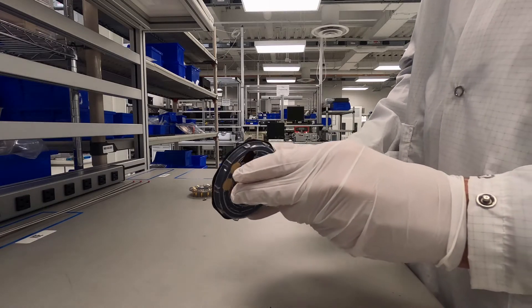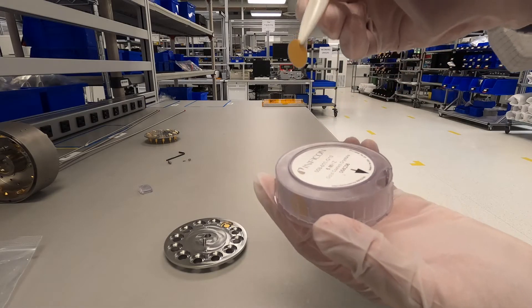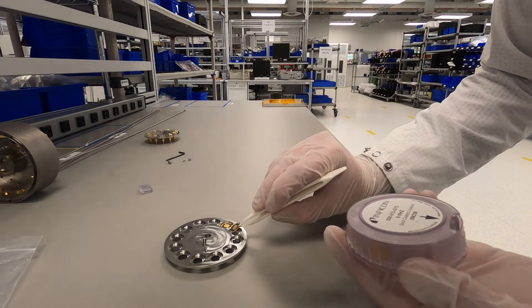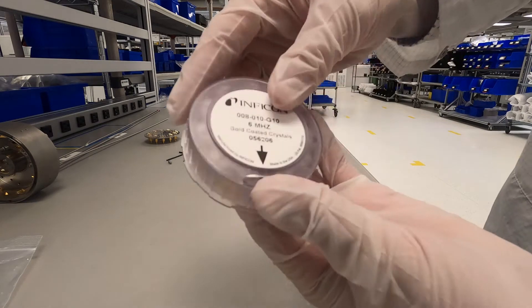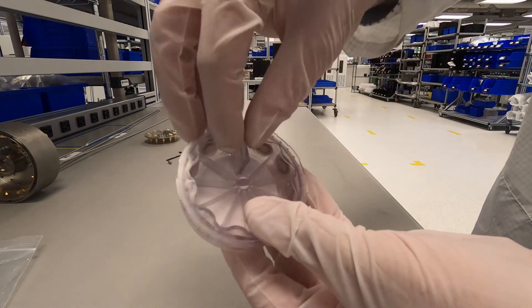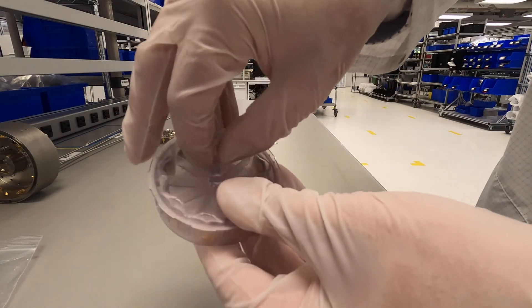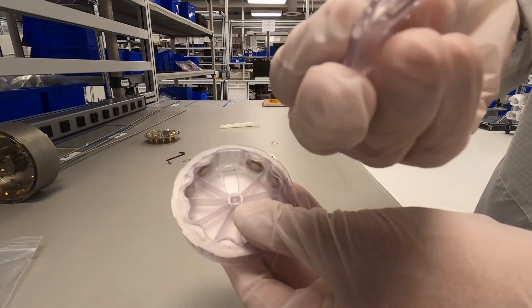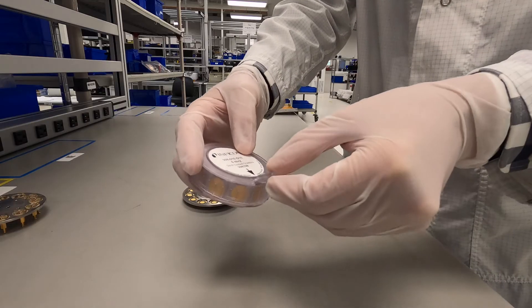When handling the crystals, it is important to not touch the crystals with your hands and use Teflon tweezers as well as gloves. The in-clean room compatible dispenser comes with a crystal transfer carrier located underneath the packaging that you can use to handle the crystals.